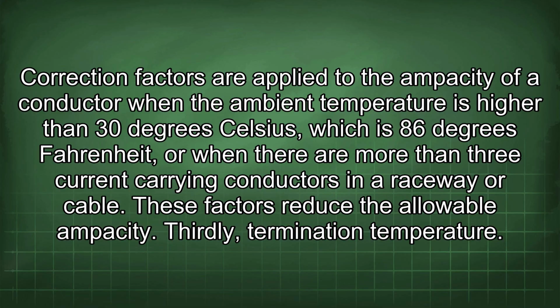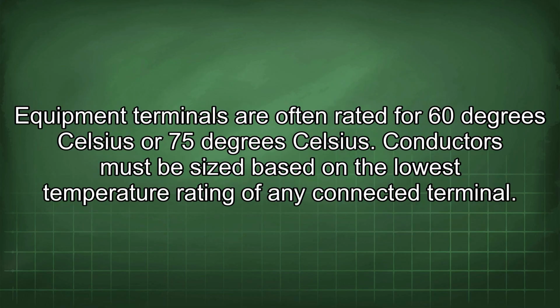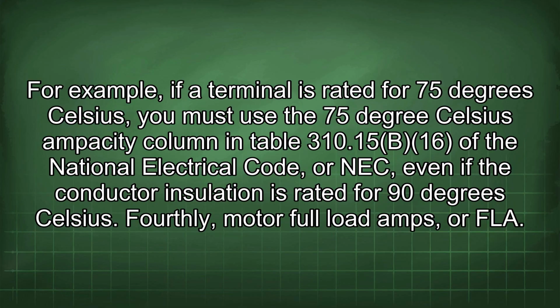Thirdly, termination temperature. Equipment terminals are often rated for 60 degrees Celsius or 75 degrees Celsius. Conductors must be sized based on the lowest temperature rating of any connected terminal. For example, if a terminal is rated for 75 degrees Celsius, you must use the 75 degrees Celsius ampacity column in Table 310.15(B)(16) of the NEC, even if the conductor insulation is rated for 90 degrees Celsius.